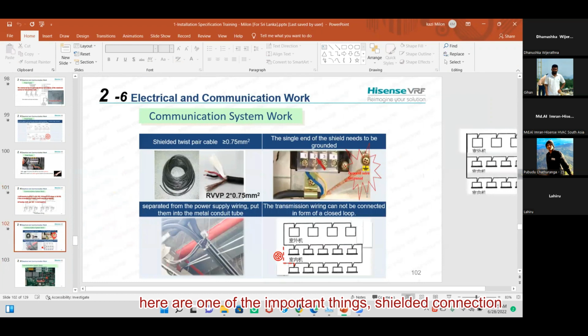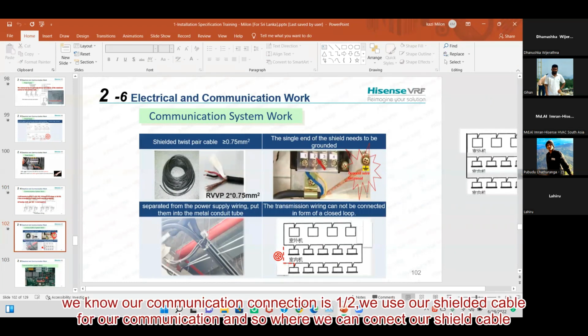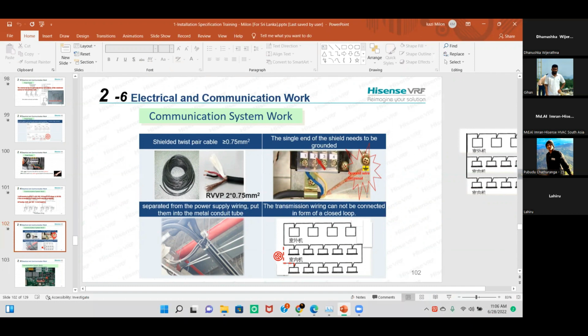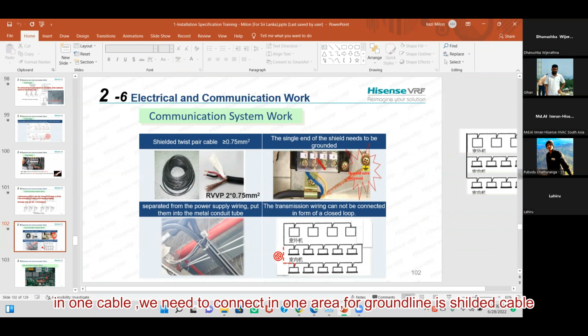Here one of the important things is the shielded connection. We know our communication connection is 1 and 2, but we use shielded cable for our communication. Where we connect our shield cable, in one cable we need to connect the shield ground line in one area.